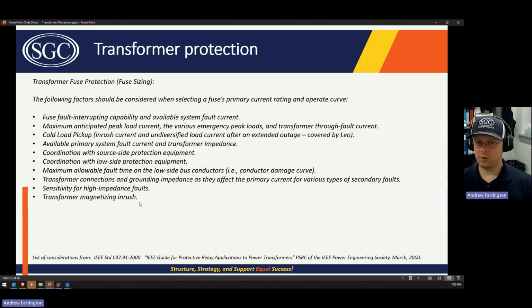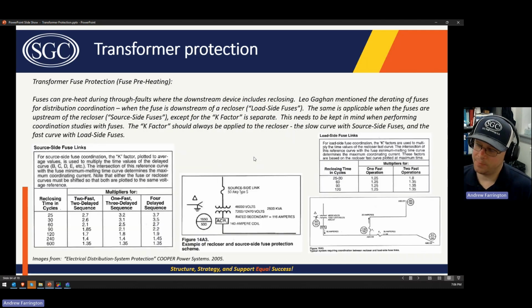This is the criteria going into sizing the fuse. I'm not an expert on this. Usually the fusing is kind of dictated by the client. For this size transformer bank, we use this type of fuse because it generally coordinates in our system and protects the transformer. I just don't have the time to get into this. I've got like 5 minutes, and I've got a lot to get through. This is transformer fuse protection to account for the fuse preheating. This is going to be on the homework.